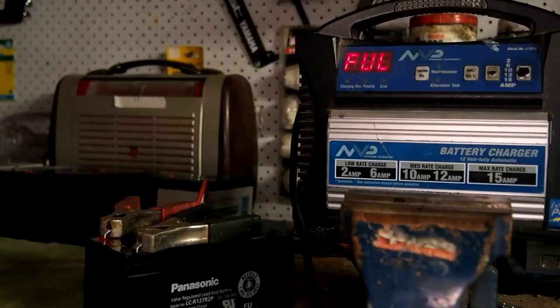This video is all about showing you how I'm going to test the batteries — both for voltage and load test them — and then secondly wire them up and actually run them in the system so everything functions and runs 24 hours a day, seven days a week, without any draw on the main system. The first thing we want to do is charge the batteries up, make sure each one is fully charged, and once they are we can do the full test and check.